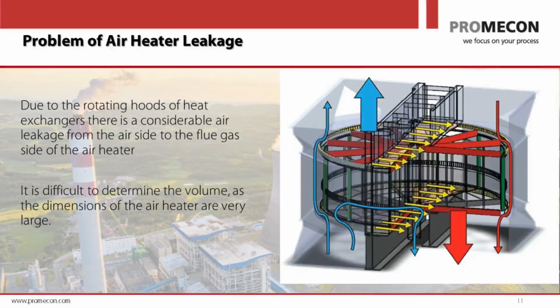So far, so good. Of course, these plates are also picking up something else. They are picking up the fly ash. They are picking up the fly ash that sticks to the plates when they rotate through the hot side, the flue gas side. So the flue gas, with all its fly ash, is not only giving the heat away to the plates, but also a considerable portion of its dust and fly ash. And this fly ash is then transported onto the cold side, where it's taken away by the cold air, and so the whole ash reaches the boiler, the mills, the burners, with the preheated airflow.